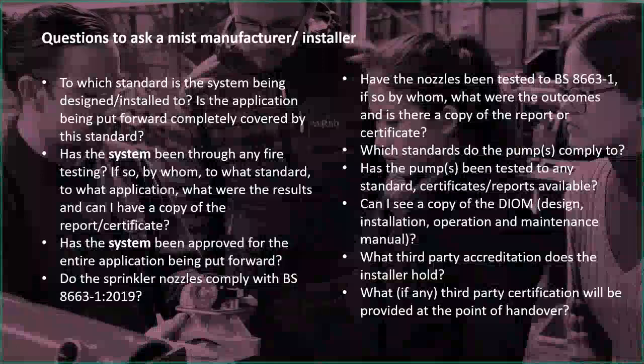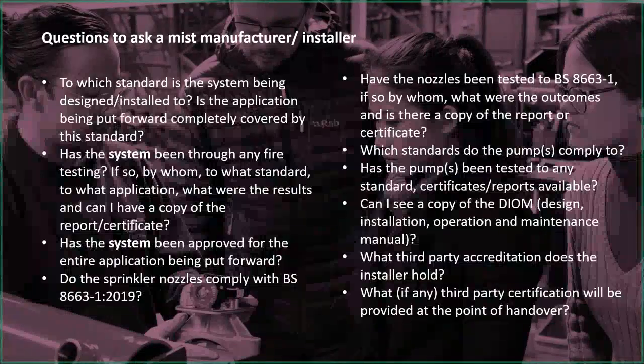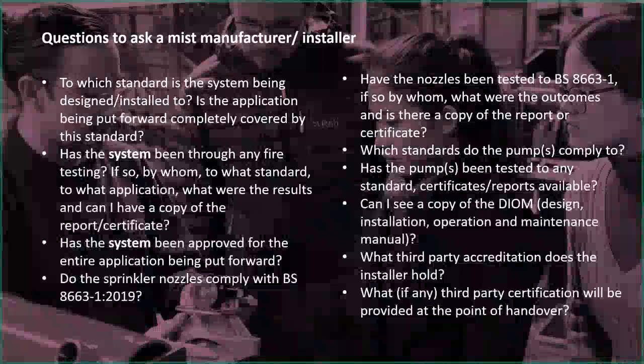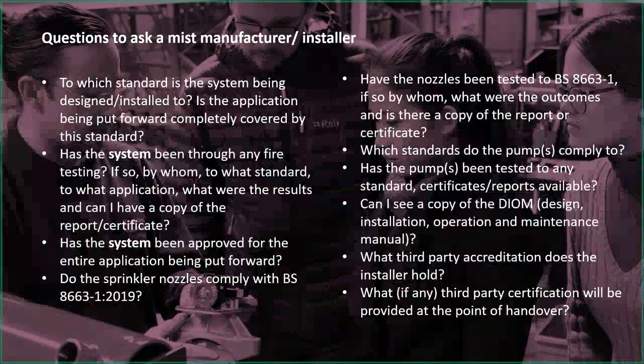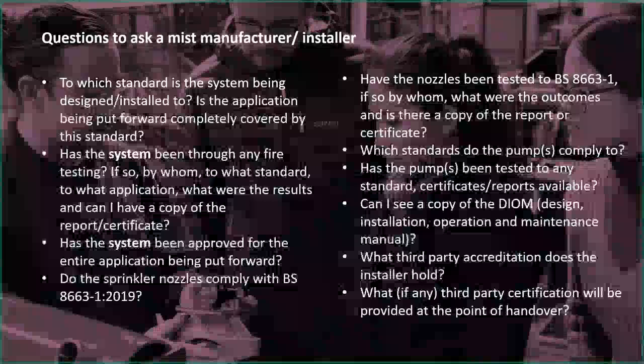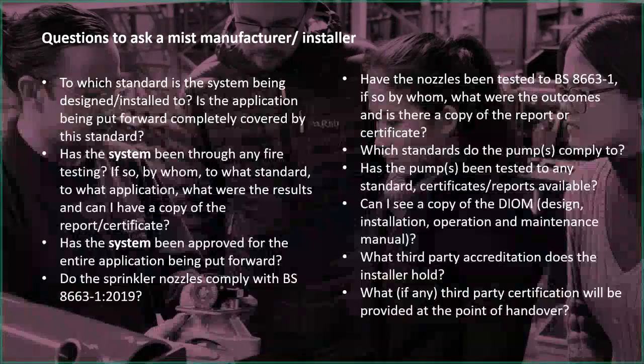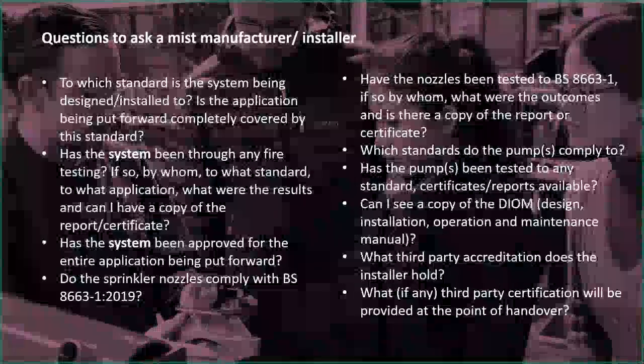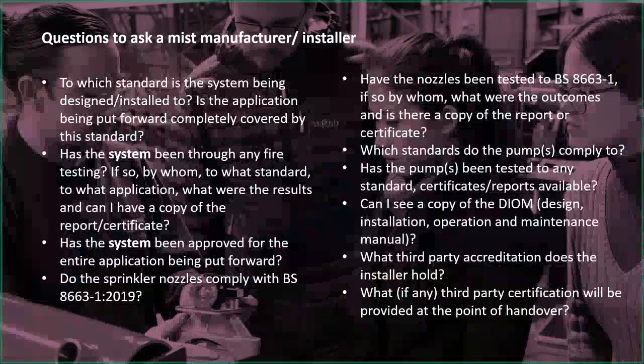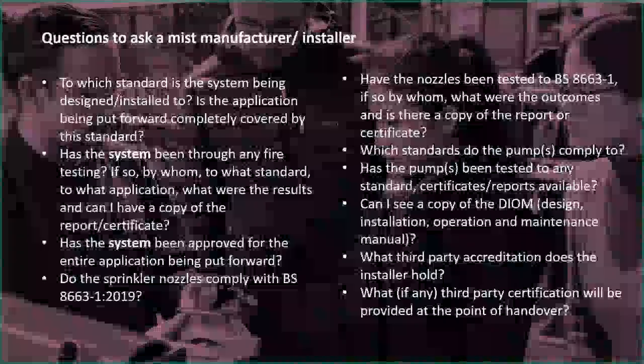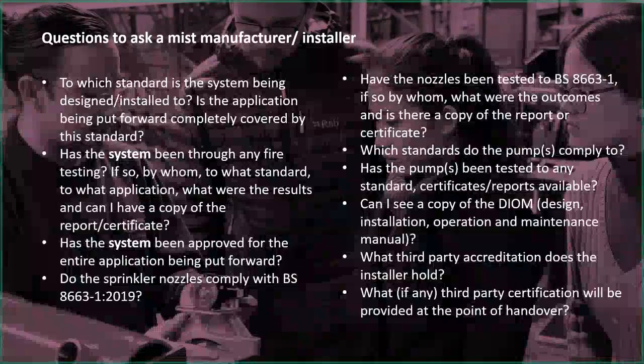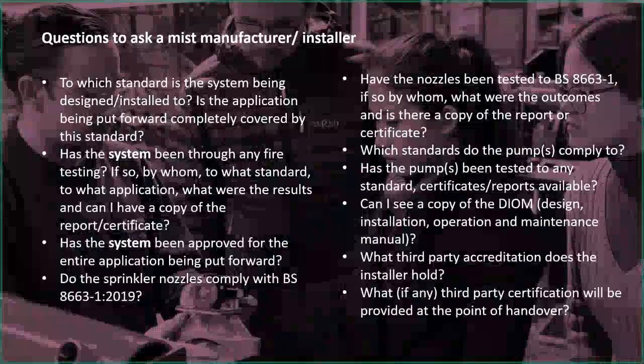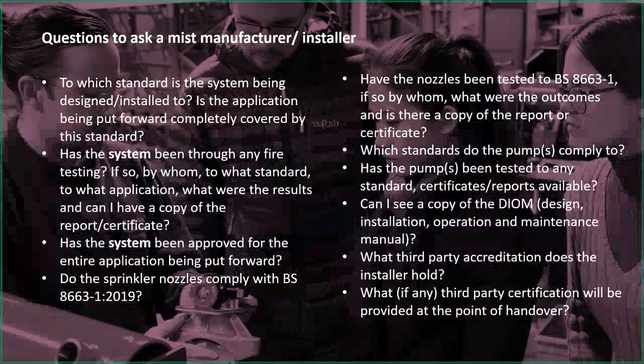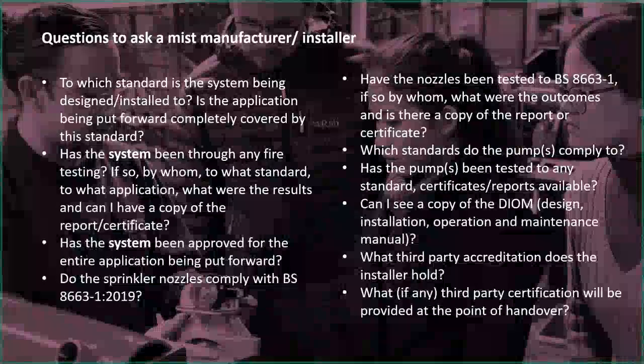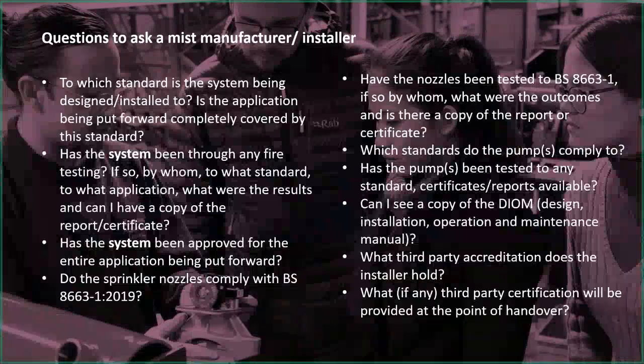How to decide which manufacturer to approach is quite difficult. In the sprinkler world, you could contact three sprinkler contractors and get very similar designs - all compliant, maybe using different manufacturers of alarm valve or groove coupling, but you'd get the same sort of system. Mist manufacturers are going to vary greatly, and they're going to tell you this is fine, it'll be perfect for that application, yes it's all approved and signed off, no problem.